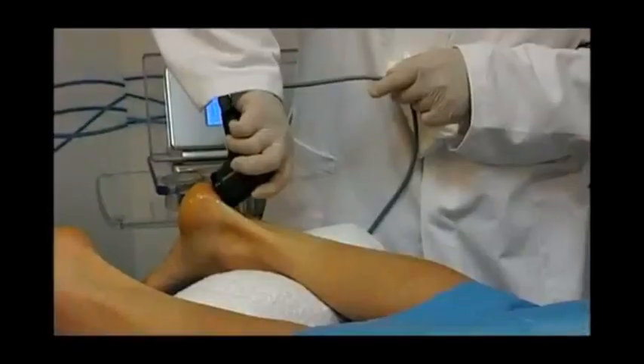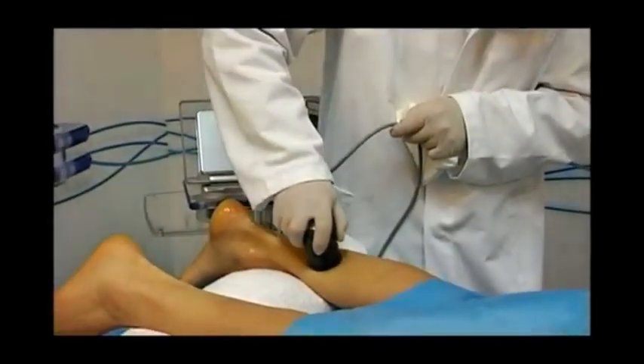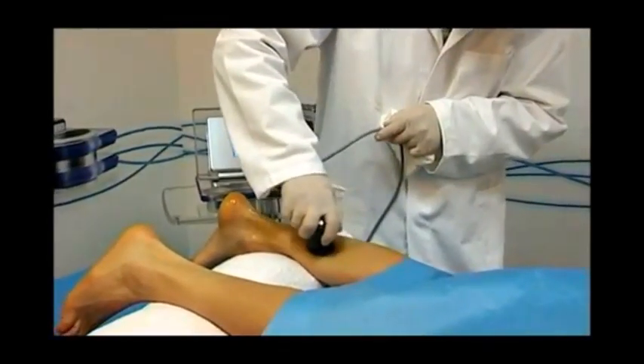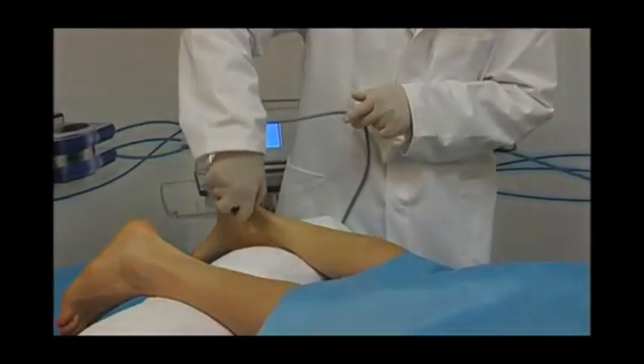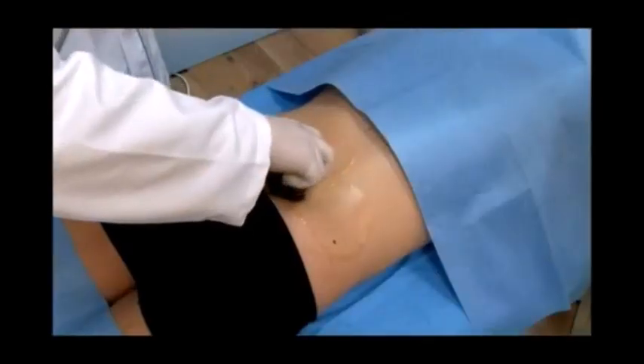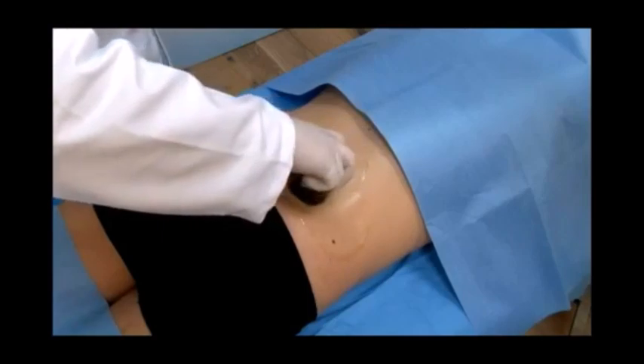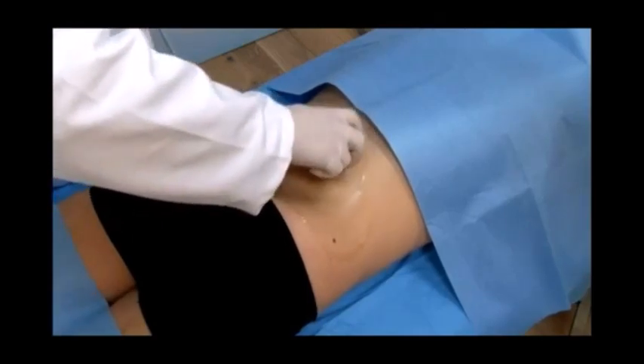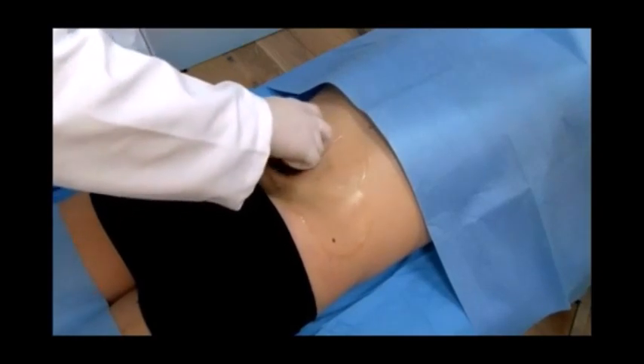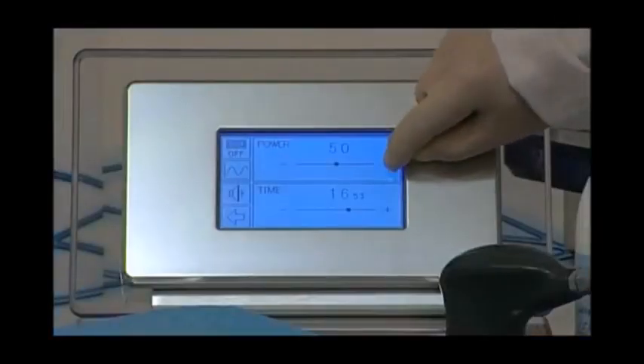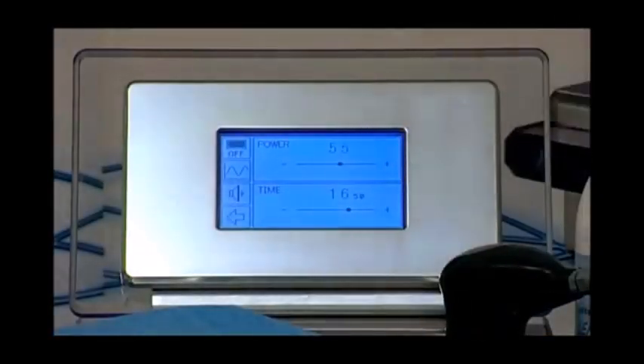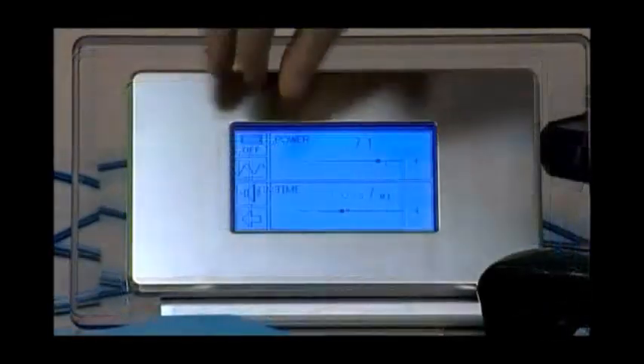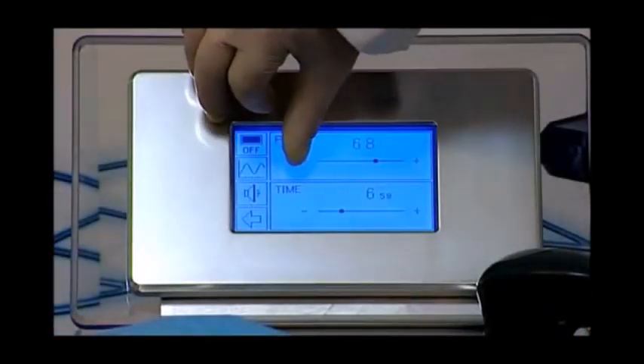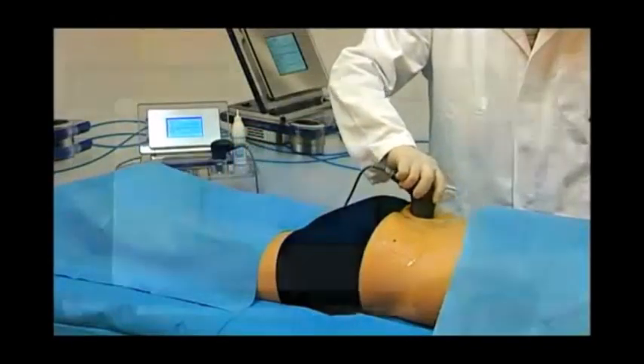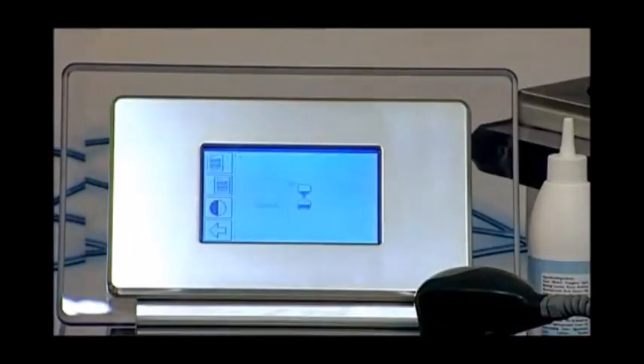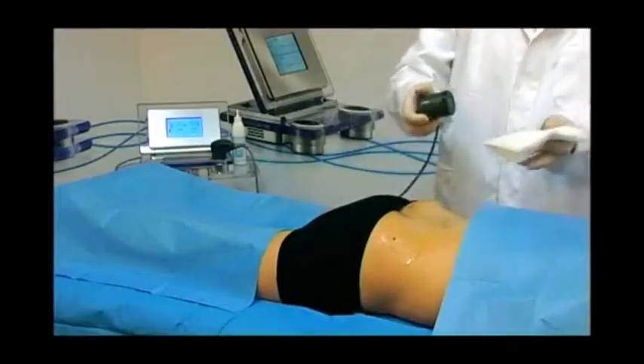In order to find the best power output setting, it is necessary to ask about the patient's sensations. The patient must feel diffused heat on the treated area, followed in some cases by a tingling sensation. Increase power output in 5% increments every 30 seconds until you reach the best power output setting. If, during treatment, the patient complains about pain or too much heat, decrease the power output by 5%. When treatment is completed, carefully clean the hand probe.